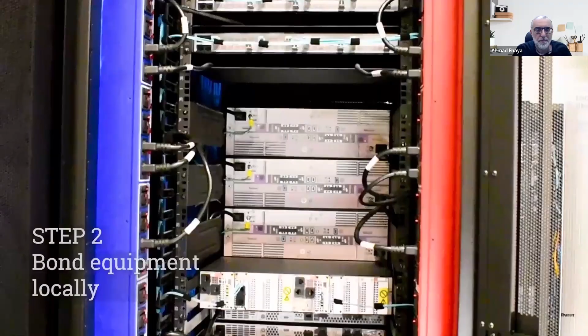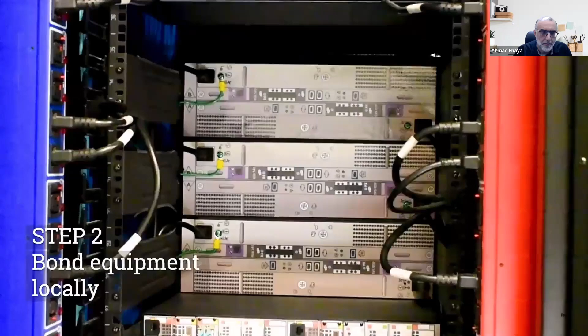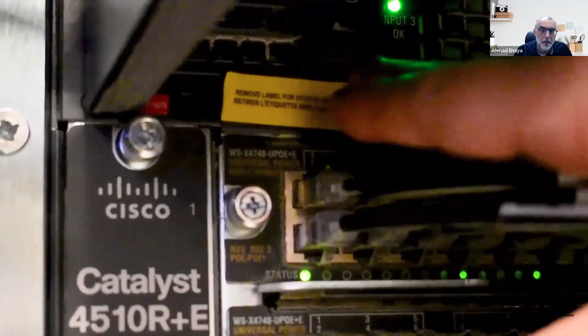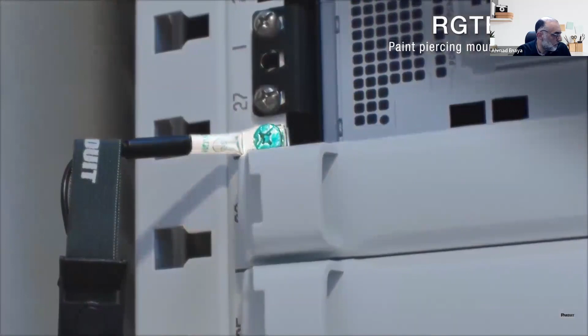the same level. Step 2 is to bond your equipment locally to the cabinet or rack. This should always be done per the manufacturer's instructions, but TIA requires this to be done in a visually verifiable manner. It is easiest to use a green insulated jumper and connect the equipment to a metallic rail strip or horizontal bus bar. If the equipment has metal flanges instead of a landing zone for a 2-hole lug, make sure to use paint-piercing mounting hardware and to bond the flange to the rack or cabinet.